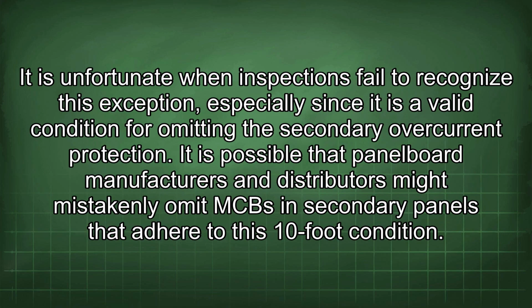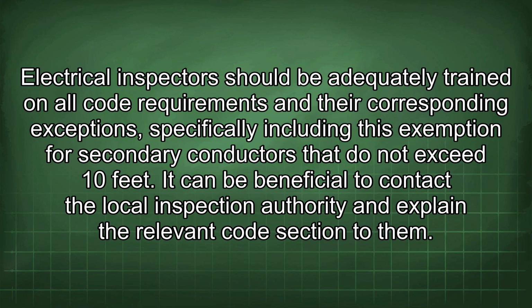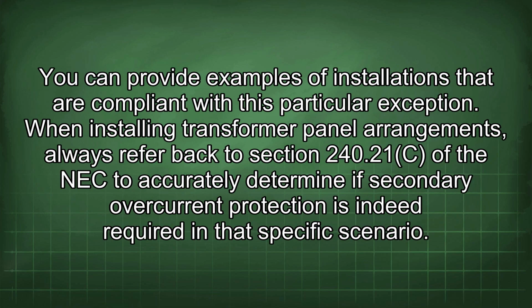It is unfortunate when inspectors fail to recognize this exception, especially since it is a valid condition for omitting this secondary overcurrent protection. It is possible that panel board manufacturers and distributors might mistakenly omit the MCB in secondary panels that adhere to this 10-foot condition. Electrical inspectors should be adequately trained on all code requirements and their corresponding exceptions, specifically including this exemption for secondary conductors that do not exceed 10 feet. It can be beneficial to contact the local inspection authority and explain the relevant code section to them. You can provide examples of installations that are compliant with this particular exception.